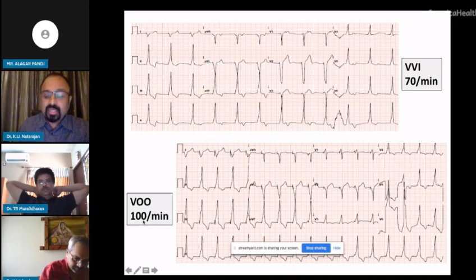It also gives us information about the battery status. If a pacemaker's VOO rate is very low, for example, if it is a Medtronic pacemaker, the VOO rate is expected to be 85. If it is much lower than 85, you know that the battery status is not good. That is another advantage of the magnet. So this is just to tell you that a VVI pacemaker at 70, on keeping a magnet, goes into VOO at 100 per minute. Likewise, an AAI pacemaker at 70 per minute here, when you keep a magnet, increases its rate to 85. It depends on the make. Boston Scientific will become 100, St. Jude will have 100, Medtronic will have 85.